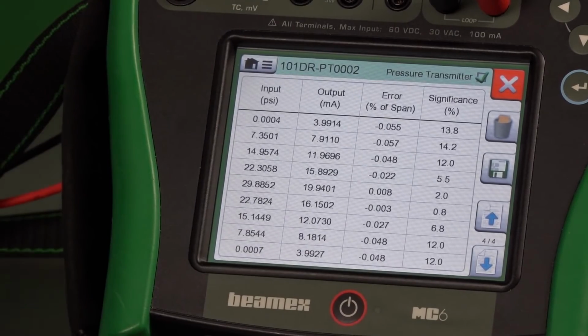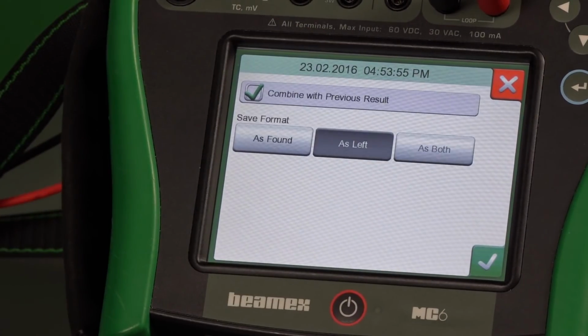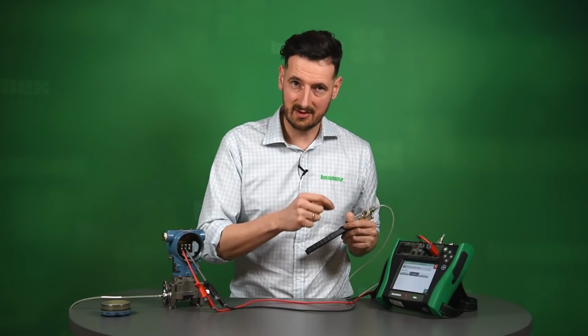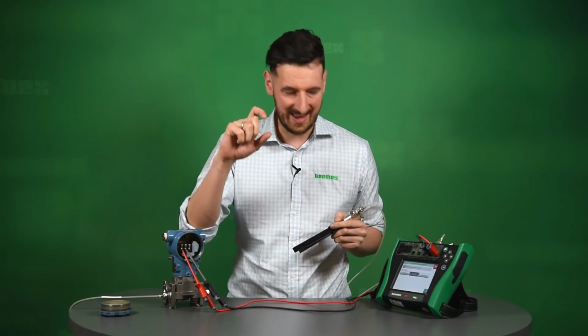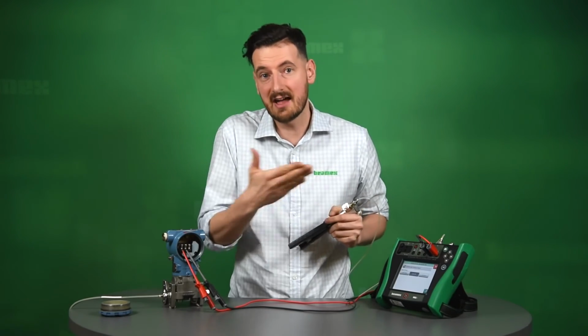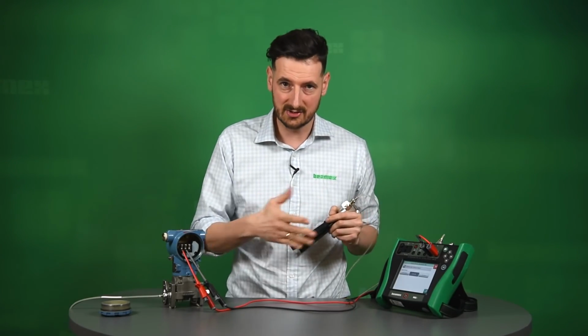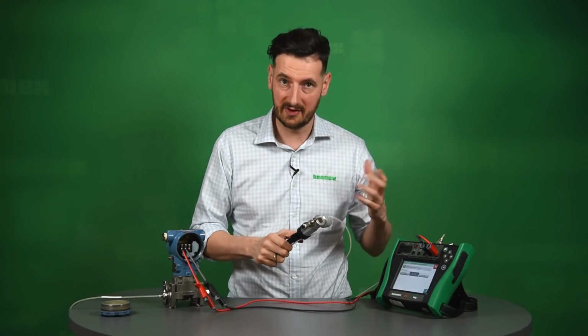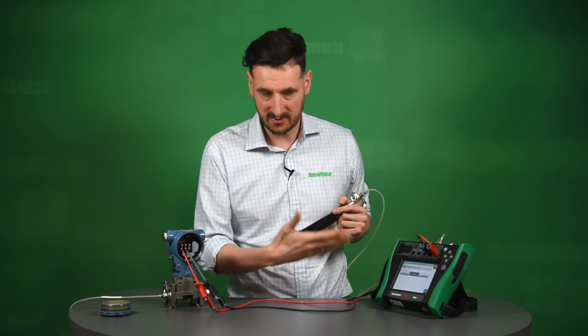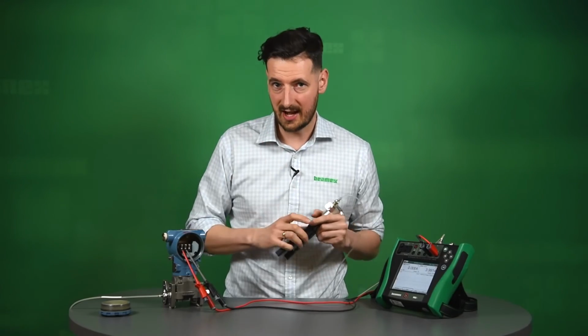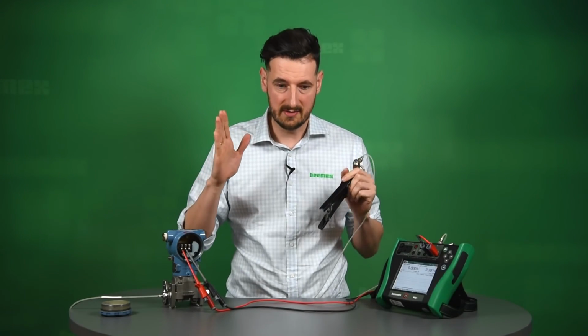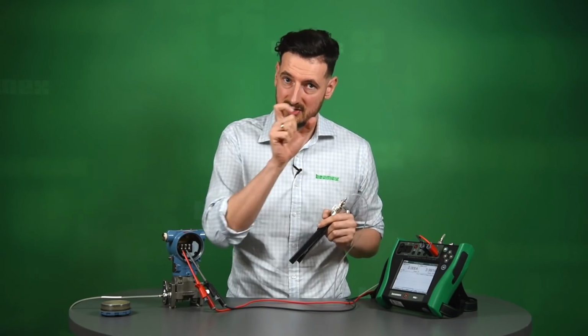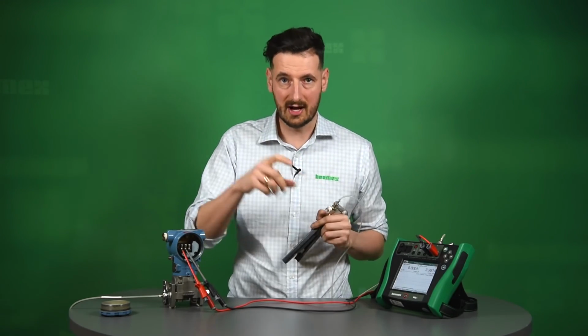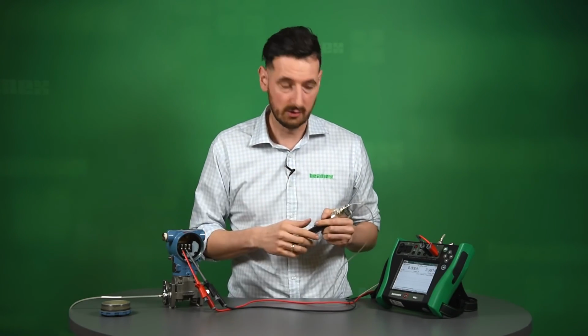Again, we can put notes, etc. We can see the graph and the numbers behind the graph. Right now, we can also save and combine this as left calibration, the calibration after adjusting, with the calibration that we did as found, which was the failed calibration. So the calibrator is actually suggesting that we should do that. So let's do that. That's allowing us to actually see on its certificate both as found and as left, two graphs, one failing, one passing. It's going to look nice.